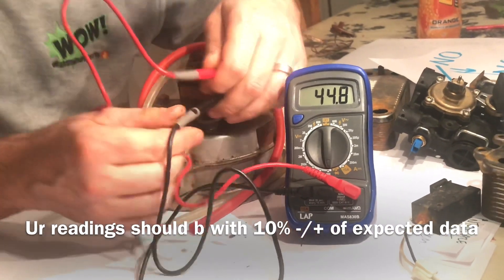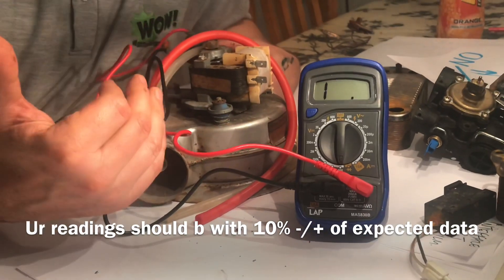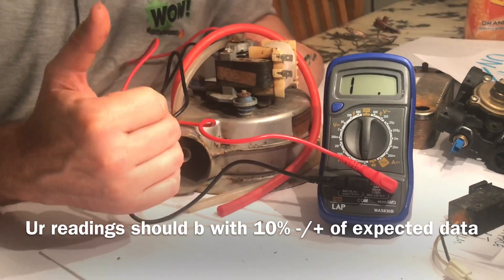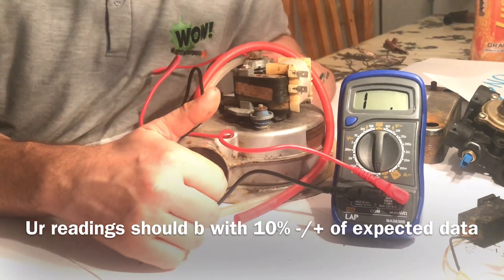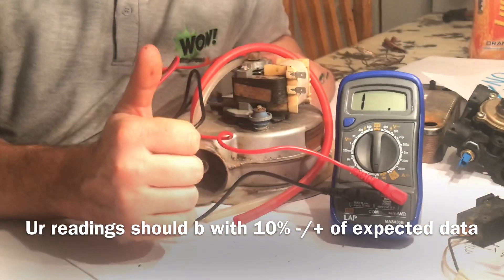45 ohms. And then with that information, what you would do is check the resistance readings, what it should be, against the manufacturer's instructions. It's going to be within 10%, so plus or minus either way.